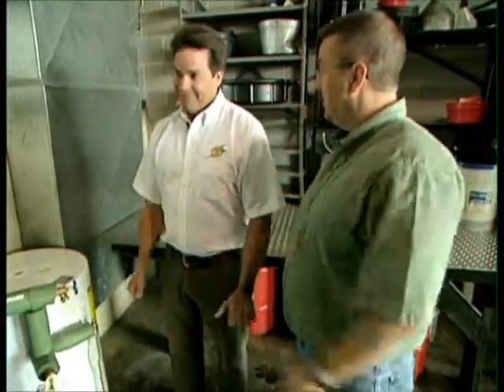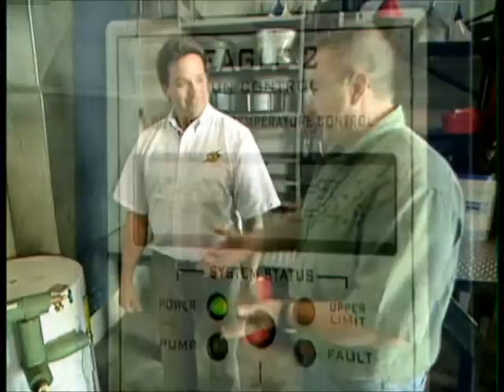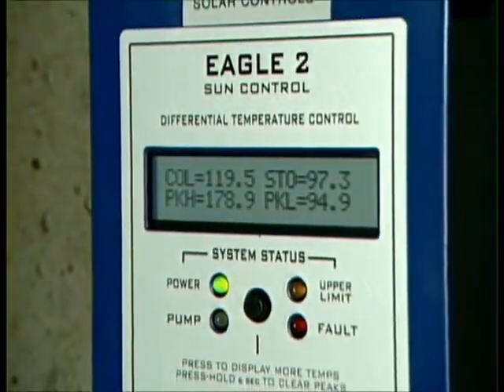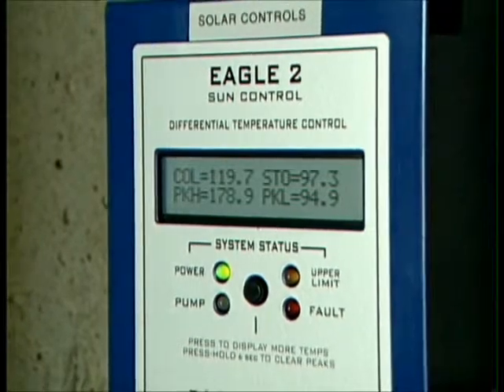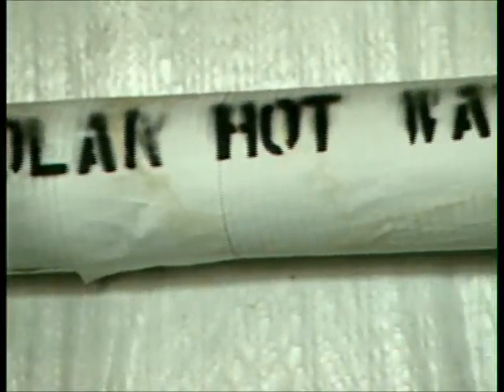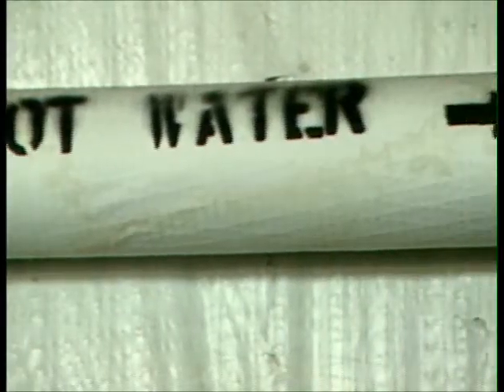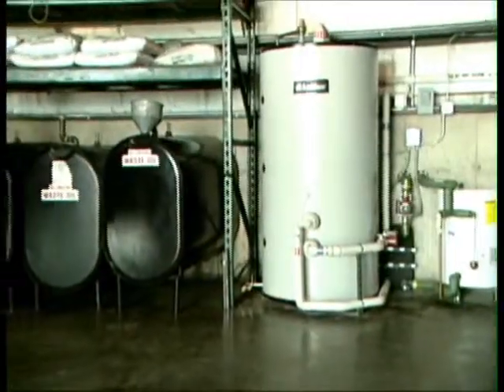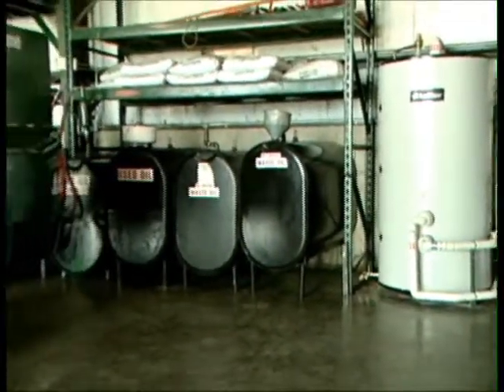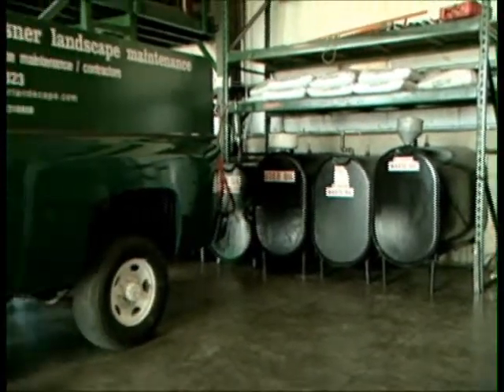And over the course of a 4 to 6 hour sun period, we can raise this tank to 180 degrees. 180 degrees, so you can theoretically be bringing well water, again, 55 degrees, and raising it that much. So it's a very efficient system. And then that heat energy from the water can be sent to various parts of the building for either heating or domestic potable water use. And here, are they just using it for basic the lav or domestic water? No, they have a locker room for the showers, and they use a great deal of water that they put into their power washers to clean their equipment, trucks, landscape equipment. So it really makes sense for them.